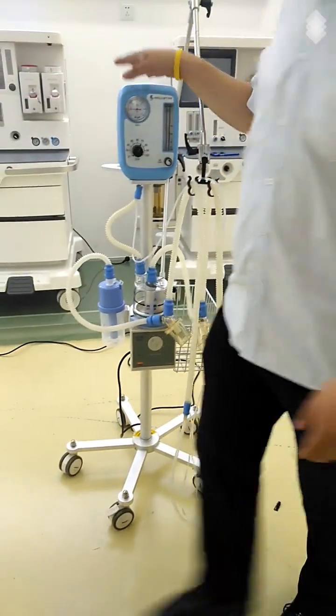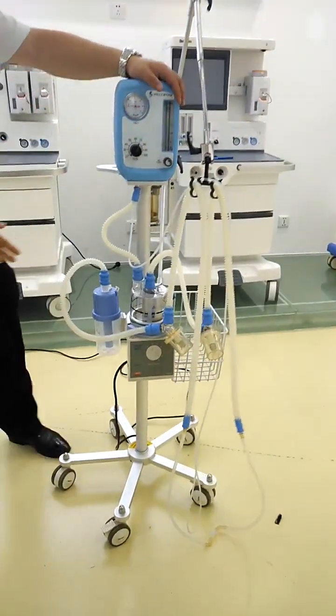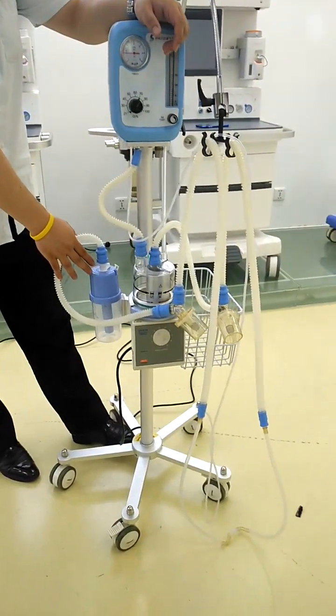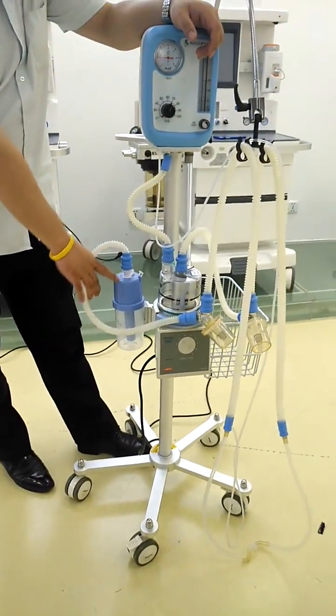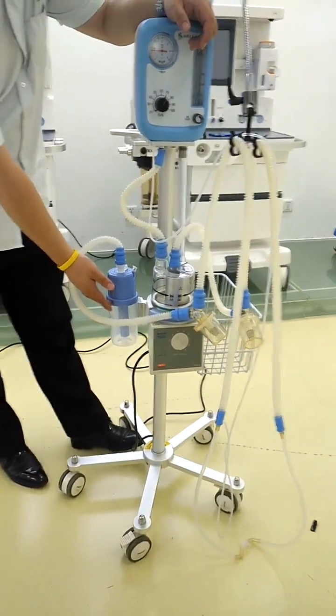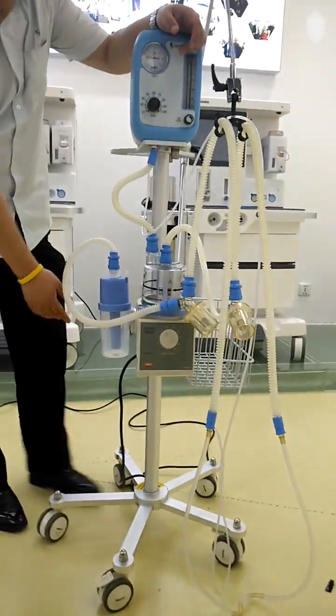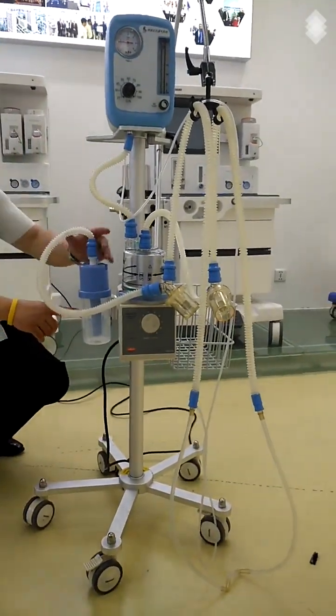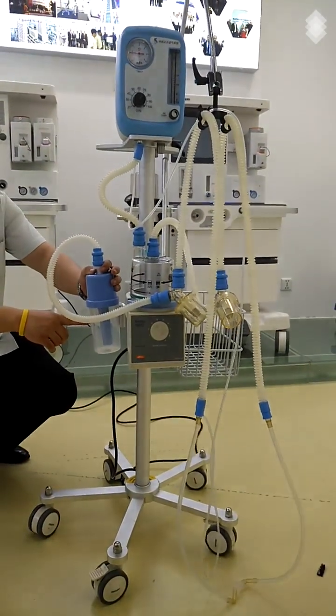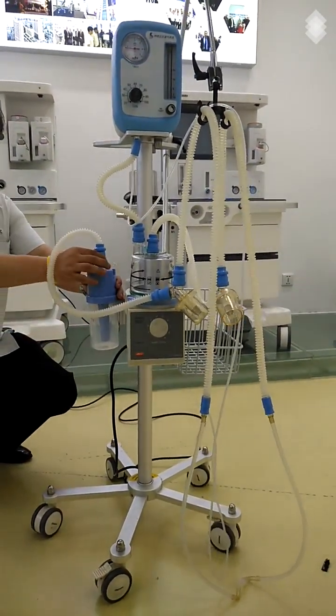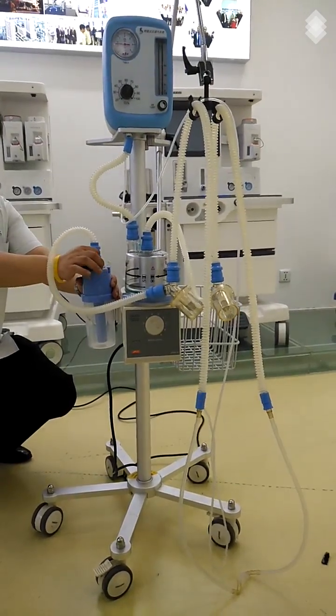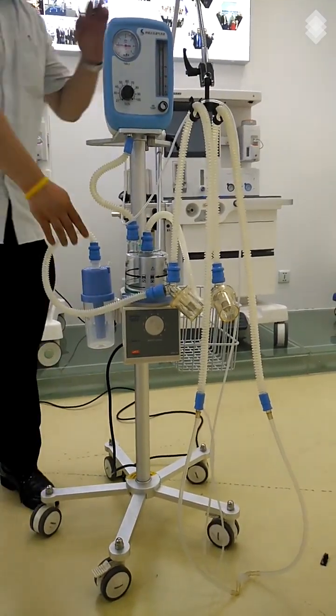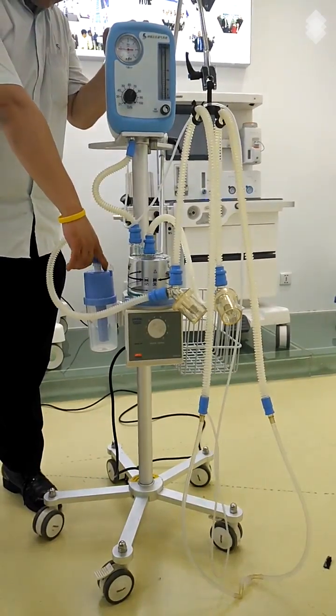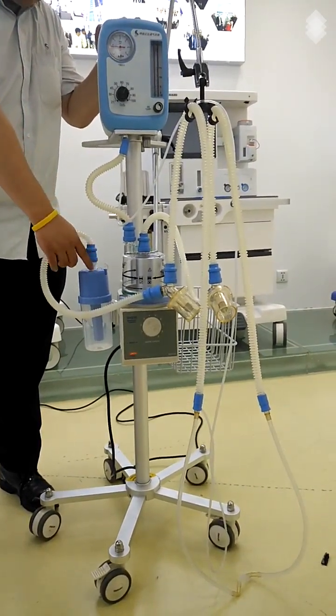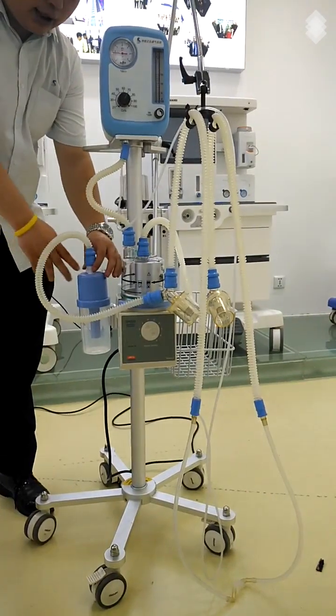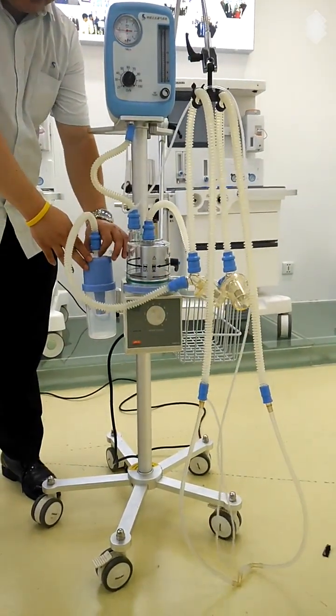For the principle of this machine, as we call it the bubble CPAP, this part is very important. This one is for adjusting the pressure, and here we are using something like a water column. Inside you can put the water in, and here you can see there is a line. The water should not be above this line, and when the water is in, with this white item we can adjust the pressure. You can see it goes from 1 to 10, so the pressure range will be from 1 to 10, and with the white item we can set it from 1 to 10 centimeters.